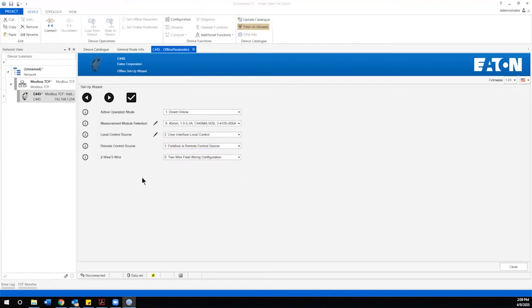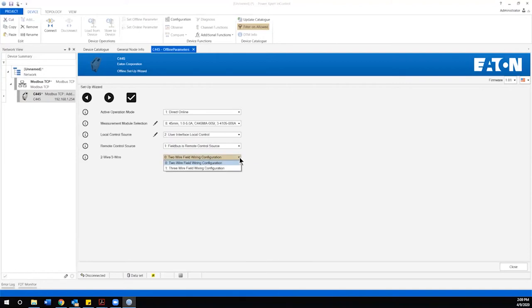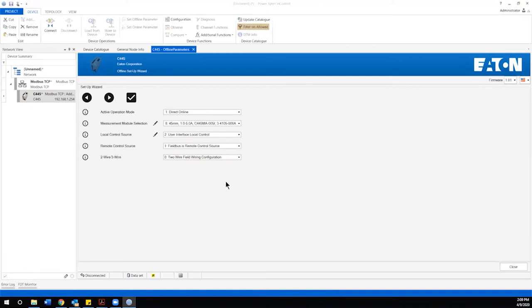The last configuration here for the screen is we need to define the methodology for starting and stopping of the starter. And we have two selections, a conventional two wire or a three wire. This speaks to the configuration of the signals or the start and stop buttons that would be associated with this. Quite commonly this is defined by the PLC programming and the outputs associated with the PLC. Let's select a two wire field operation today for this example.